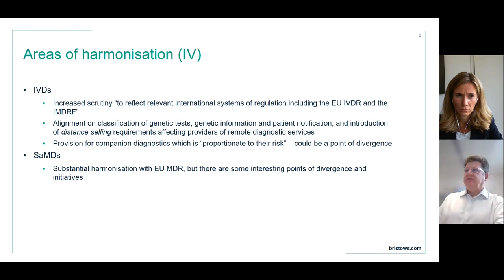We're nearly done on the areas of harmonisation. The intent with IVDs is to have increased scrutiny. At the moment, the estimate is somewhere around 10 to 15% of IVDs require the involvement of a notified body or an approved body, but the intent is to flip that around, so it'll be more like 85% of products requiring the involvement of an external body.